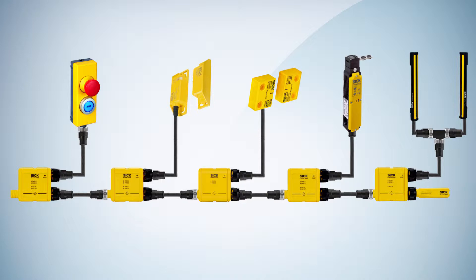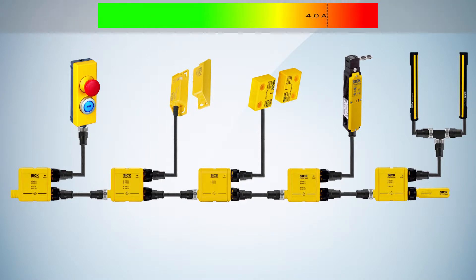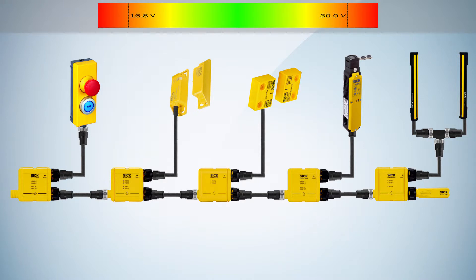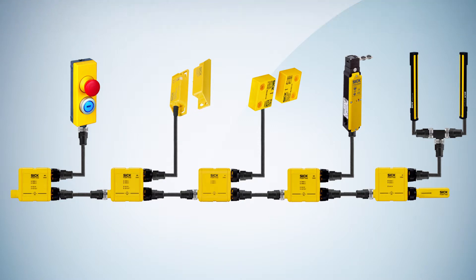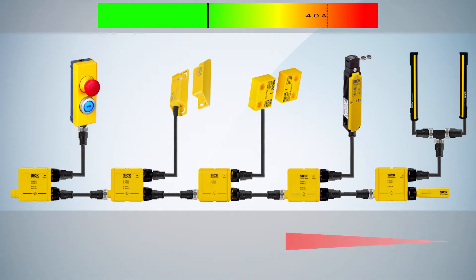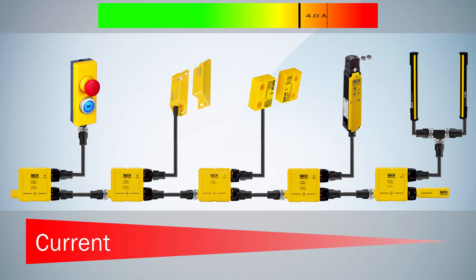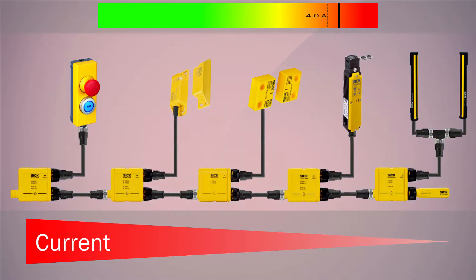Furthermore, the current and the voltage of every node have to be in a certain range. The current must not exceed the value of 4A, and the input voltage of each FlexiLoop node must be in between 16.8 to 30V. To calculate the current at a specific point of the cascade, you can simply add up the individual current values of the following devices, including the terminating element. If the current exceeds the value of 4A at any point, it reaches an unacceptable range.